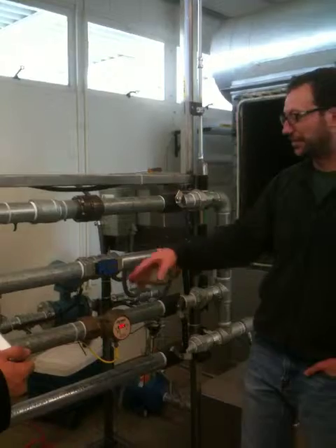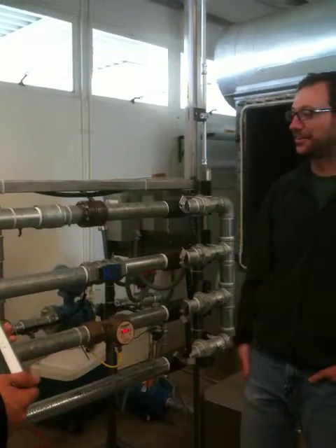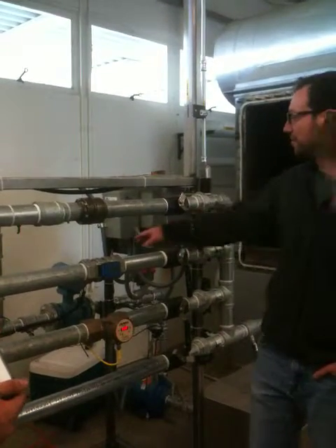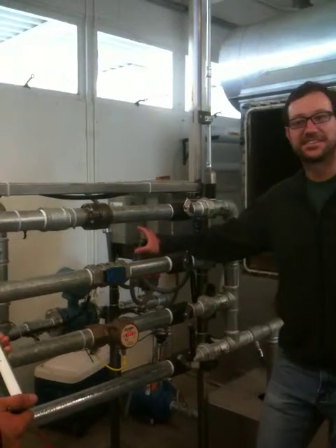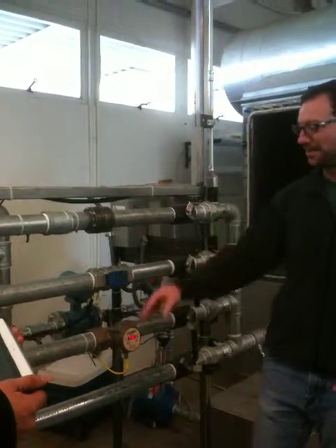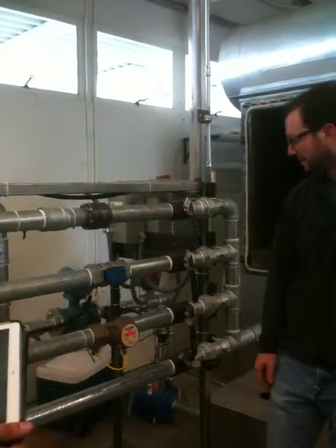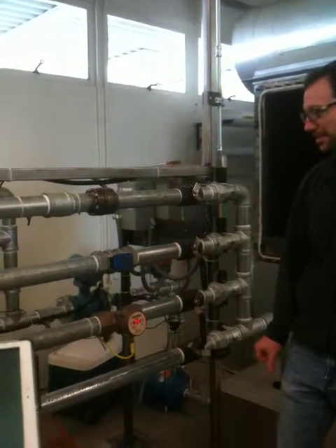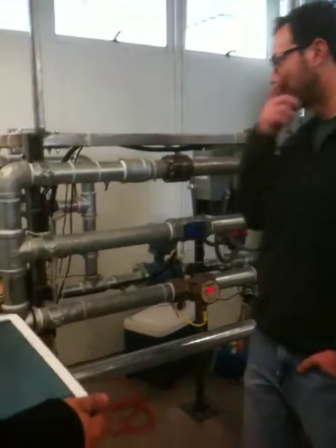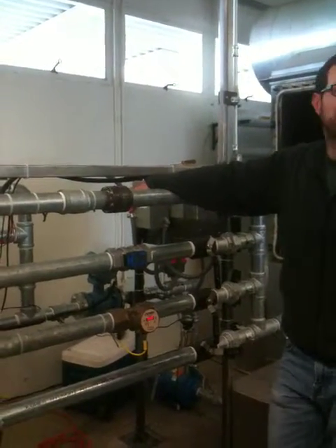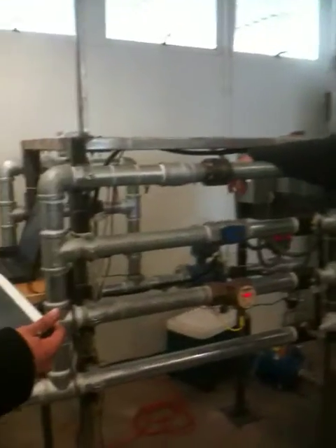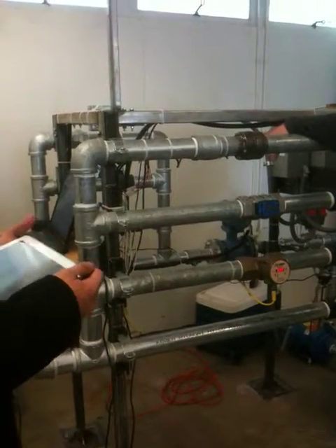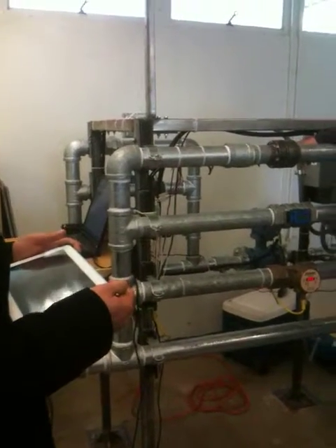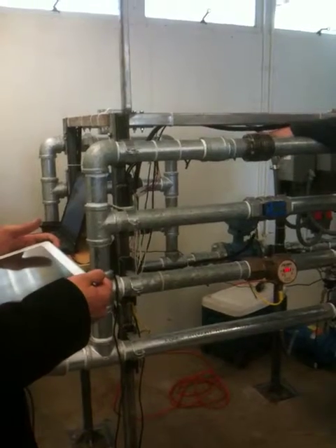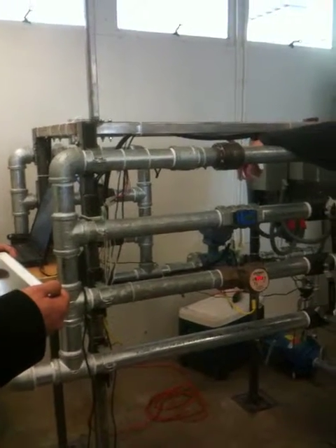And so then you can run the flow through one of these. It'll tell you what the flow rate is over there. You treat the magnetic flow meter like it's the true value, and then you see how these 3 are calibrated. And that's pretty much it. The one thing you might look for, to get the equivalent length of each of the valves should be no problem. You can do that for any flow rate. One thing you want is the flow coefficient, and that's the flow through the valve when you have 1 psi of pressure drop across it.